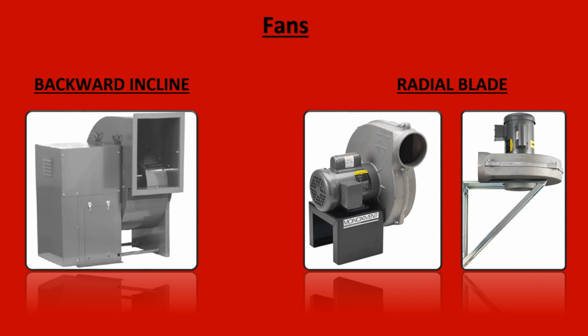On the right, the radial blade fans are ones we manufacture ourselves in Rock Island. They're aluminum cast, making them spark resistant by construction. We put a standard Baldor motor on them, but can add an explosion-proof motor if needed. These are the fans you saw mounted directly to hose reels or source capture arms, or they can go on a foot mount base or wall bracket, for use inside or outside. They range from 0.5 to 3 horsepower—an excellent quality fan at an excellent price, manufactured right in the USA in Rock Island, Illinois.